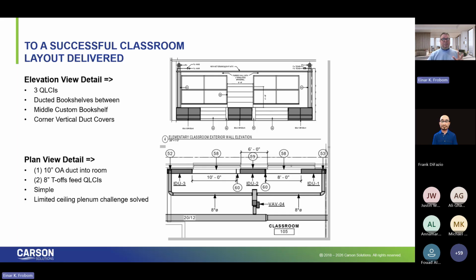It doesn't have to be this layout. What if you had a 1940s, 1950s building that had a lot of columns? That wouldn't lend itself to this nice continuous outside air duct. If you had a column, a lot of times in that example, we'll straddle that column with an outside air drop on the left and an outside air drop on the right, and then feed the outside air to your left and to your right.